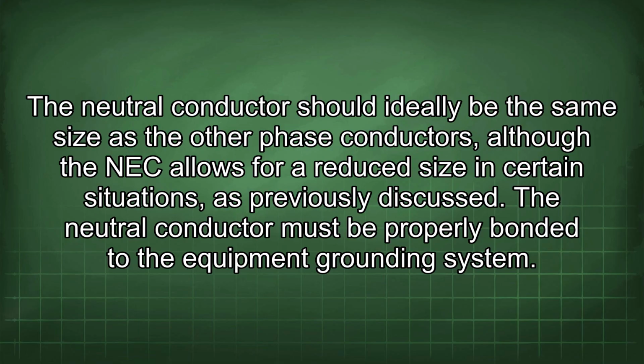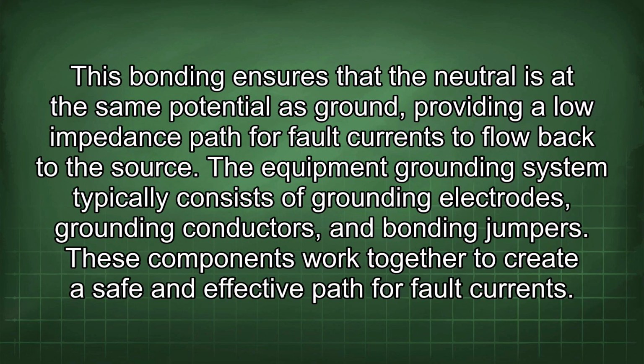The neutral conductor must be properly bonded to the equipment grounding system. This bonding ensures that the neutral is at the same potential as ground, providing a low impedance path for fault currents to flow back to the source. The equipment grounding system typically consists of grounding electrodes, grounding conductors, and bonding jumpers. These components work together to create a safe and effective path for fault currents.